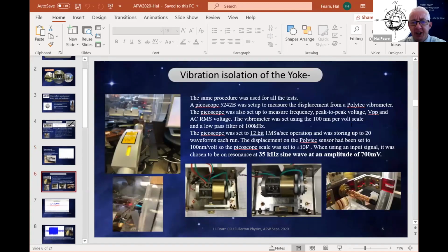Let's see what happened. Oh yes, we looked at vibration isolation. Now, at this point, we were starting to look at different brackets, different mountings for brackets, and also lots of different materials for the washers. So I'll talk a little bit about that. There was some concern that we may be looking at a vibrational artifact. So one of the very first things I did with the vibrometer, our very expensive $225,000 Polytec vibrometer, was to shine the thing at the Faraday cage just to see what the motion of the Faraday cage was, and then shine it on the beam arm just off to the left of the Faraday cage.